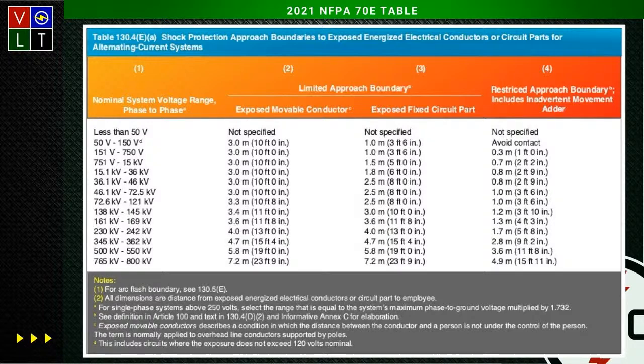Now, once I determine what the arc flash boundary is, the arc flash boundary can be less than that 3.5 foot, or it can be more. And if it's more, then the barricade moves out to that area.